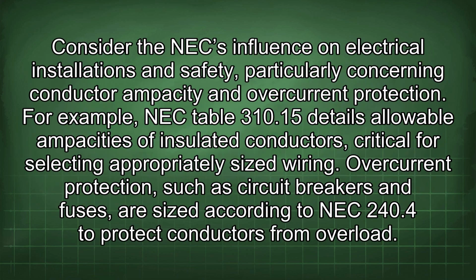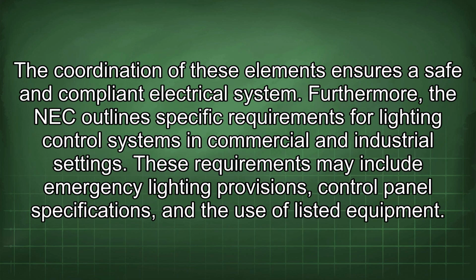Consider the NEC influence on electrical installations and safety, particularly concerning conductor ampacity and overcurrent protection. For example, NEC Table 310.15 details allowable ampacities of insulated conductors, critical for selecting appropriately sized wiring. Overcurrent protection, such as circuit breakers and fuses, are sized according to NEC 240.4 to protect conductors from overload. The coordination of these elements ensures a safe and compliant electrical system.